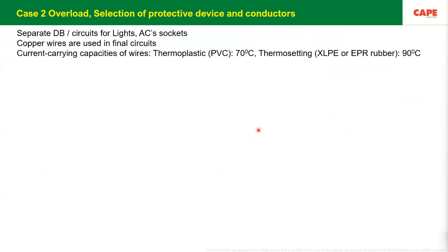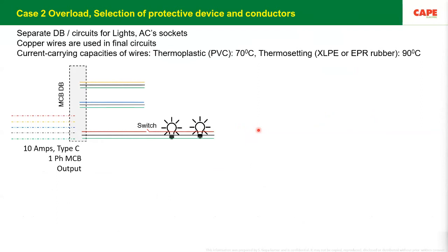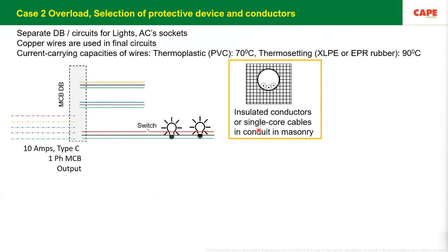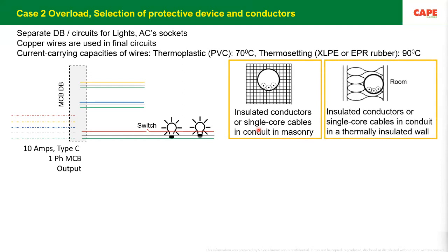That means once the current is more than the designed current, the device is supposed to trip. So instead of calling an accident due to an overload, we should start calling it an accident due to non-disconnection of a protective device, or non-operation of a protective device. We have to change the term a little bit. Only if we start calling this a non-operation of a protective device will people start realizing the seriousness of selecting the appropriate device and putting it into the circuit.